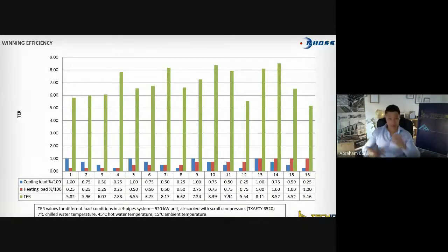The real advantage of having inverter facilities in the chiller is the seasonal one. You can say, I'm in middle season, I'm entering winter, but I still have a demand of cooling. So my chiller is running at 25, 30, 40%. So you calculate that with your weather data and you get your seasonal efficiency. That is when we start to see the real advantage of inverter. I know it's not directly related to EXP. It will also apply to EXP, but it's something to keep in mind.